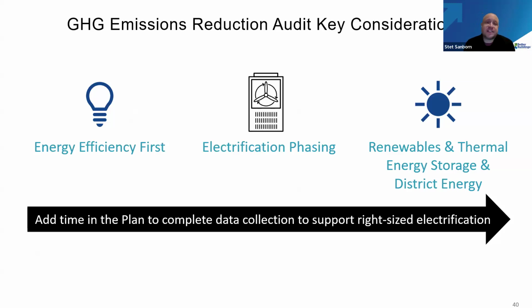Part of that leads into phasing the work—we don't have to do everything all at once. But the most important thing, which I want to stress, is to collect data so your engineering team can do a better design. If you can give us a year's worth of hourly heating use, by putting a BTU meter on your boiler and running it for a year, I can guarantee your engineering team will come up with a better solution than just throwing an oversized heat pump at the project, which would likely have turndown issues and capacity challenges.